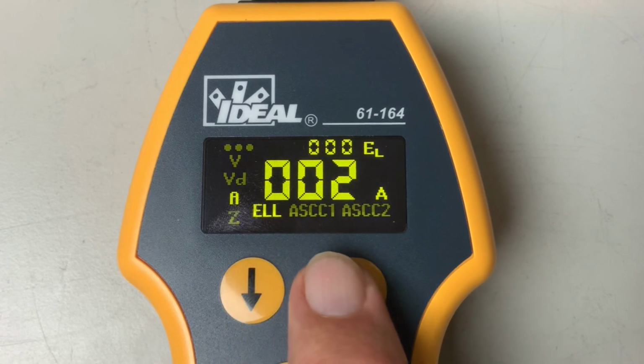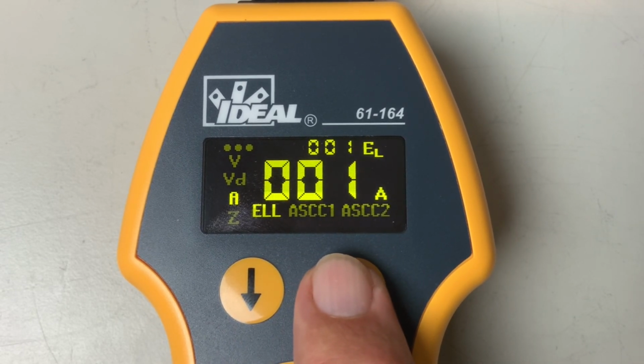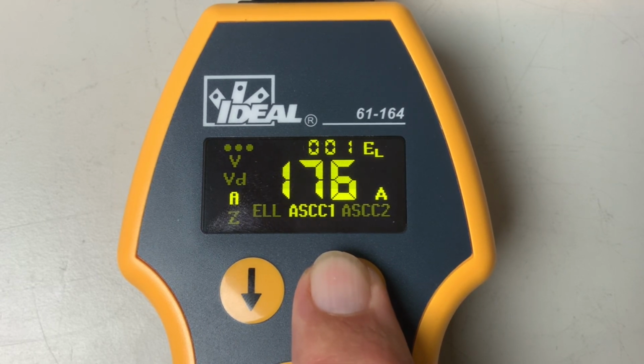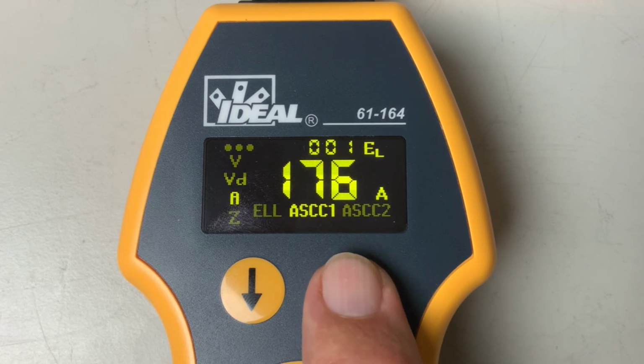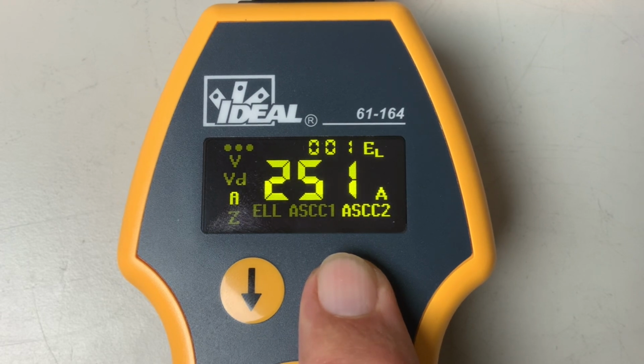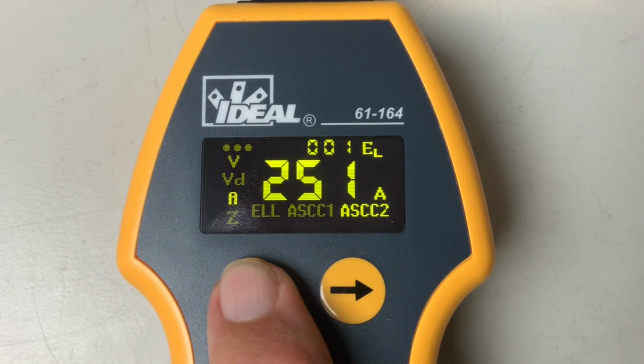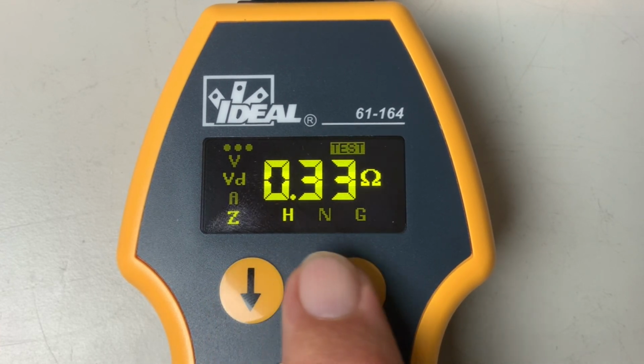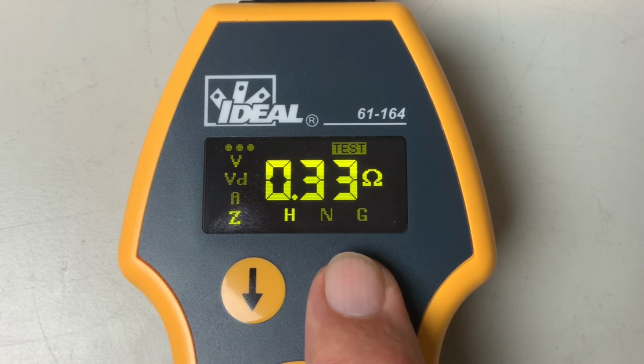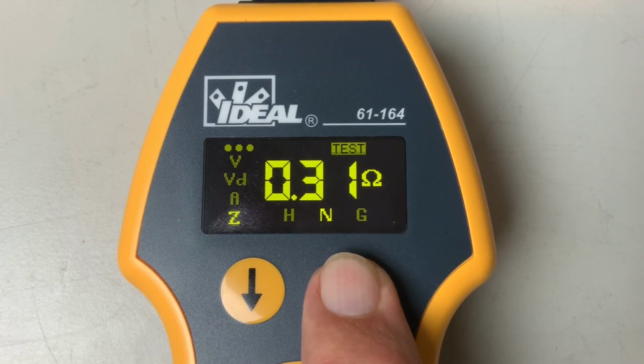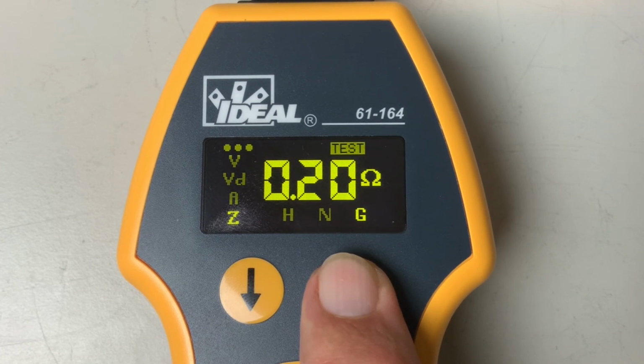The next screen is amperage. ELL stands for estimated load on the line. It kind of tells you how much current is being drawn on that particular breaker. There's some issues with that. Next is available short circuit current 1 and then available short circuit current 2. It basically tells you the amount of current that can be drawn on the wiring if somebody shorted out your plug. I don't know what you care about that for, but it's on here. Finally, you have impedance, which is the actual resistance of your hot, neutral, and ground wire. That's very important when you're looking for wiring errors and other problems, and we'll see how accurate that is and cover that in a little bit more detail next.